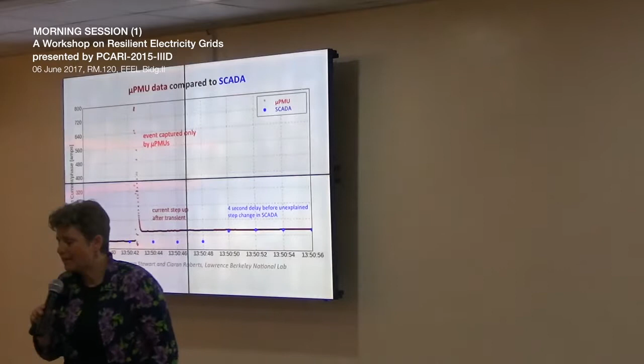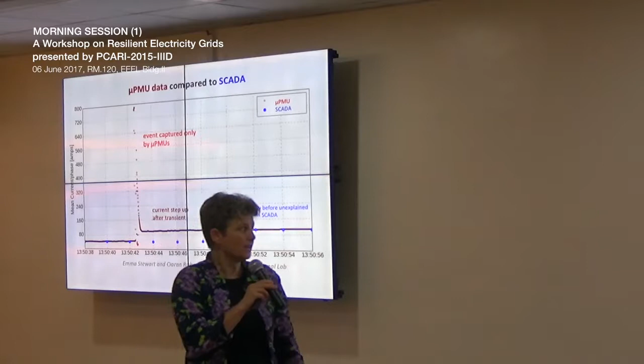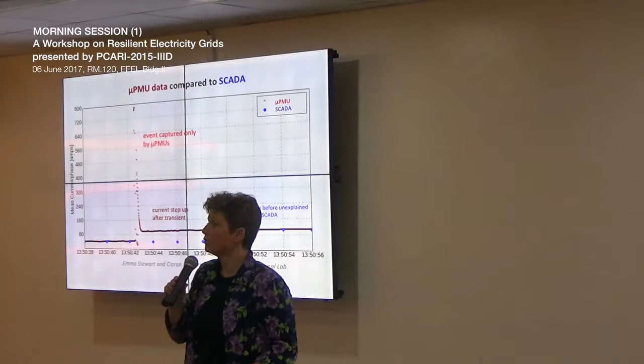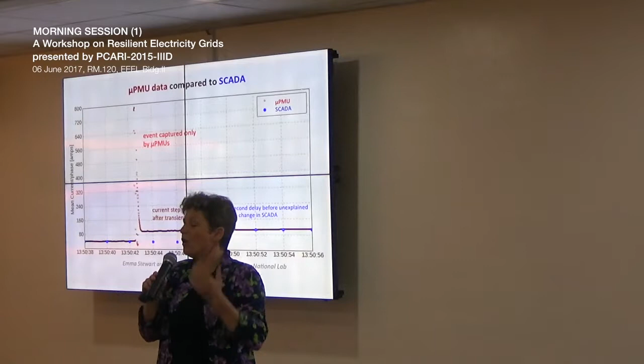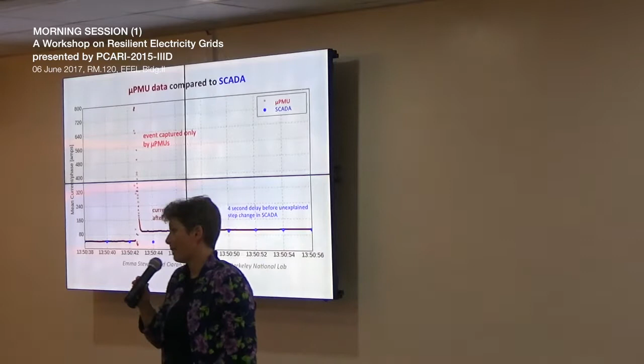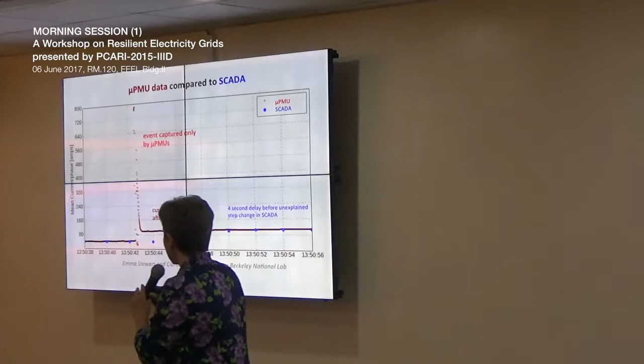But even with SCADA installed, the SCADA measurements are these blue dots. So in this particular example, this is actually good SCADA data, every 2 seconds you have a blue dot. And it just shows that, well, sometime in the afternoon at about 13:50, the current stepped up. But you have no idea that what actually happened in between was this big current spike to 800 amps. That may or may not be something you want to worry about. So with the micro-PMUs, we're able to capture that transient.